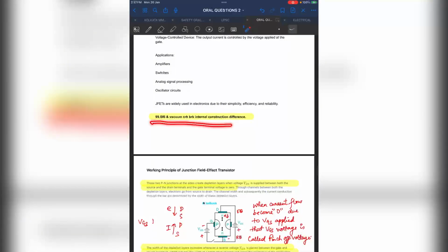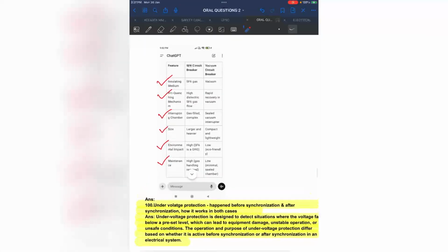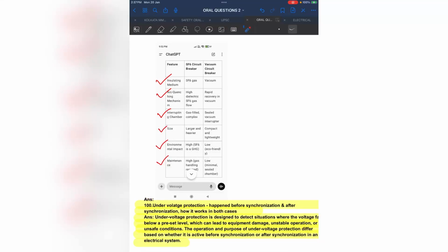SF6 and vacuum circuit breaker internal construction difference. What is the difference between the SF6 and vacuum circuit breaker? In an SF6 breaker, the insulating material is basically SF6 gas, and in a vacuum circuit breaker there is a vacuum. Because we are using vacuum for arc quenching in one, and gas for arc quenching in the other.